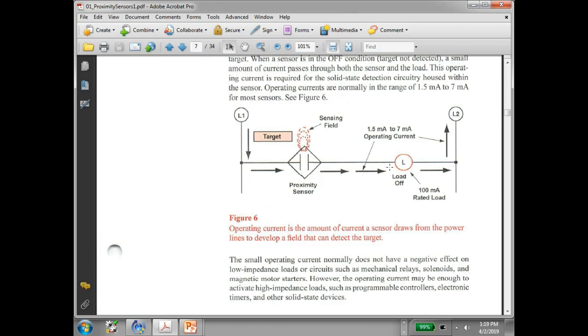And then we have what they call the holding current. You asked what you would measure for operating if it's a three-wire sensor. We would have another lead coming over here and going right there, right? On a three-wire sensor, if I was going to measure the operating current, I would measure it right here, because that's truly what's causing the sensor to operate. That makes sense now? That's a three-wire, yeah.